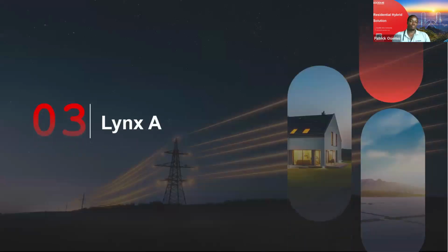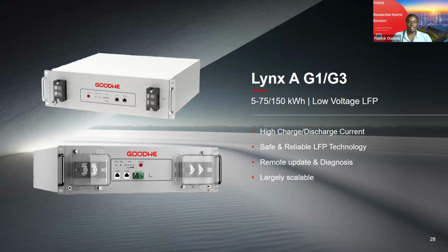On that note, I will take you through the Lynx A lithium-ion battery, and that's how it looks. There are two versions: the upper one is the Lynx A Gen 1, and the lower one is the Lynx A Generation 3. Each module is 5 kilowatt hour. The Gen 1 can be scaled up in parallel to 15 pieces for 75 kilowatt hour, and the Gen 3 can be scaled up to 30 pieces for 150 kilowatt hour. These batteries charge and discharge at high currents, and I'll look at the data sheets later on. They're safe and reliable because they use lithium-ion technology. GoodWe is also capable of remotely upgrading and diagnosing the battery, so upgrading the firmware and also diagnosing it remotely. And they are largely scalable. So that's the Lynx A Generation 1 and Generation 3.